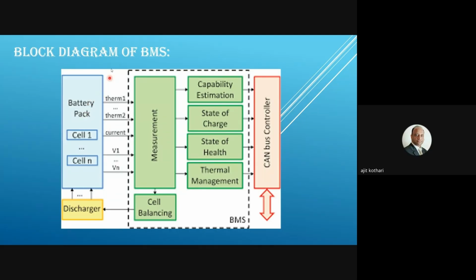So these are the sensing circuits connected to BMS, which monitors temperature, measures voltages and current. This measurement unit converts the analog signal into digital, and there are other computations inside the BMS, like state of charge and state of health, computed by additional circuits depending on how much the battery pack got charged with this current and for how many times.